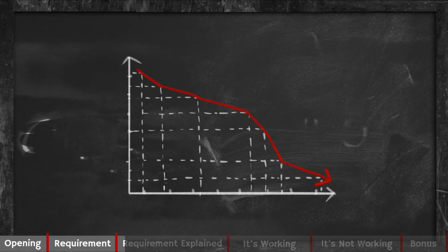The definition of overkill is a sterilization process that demonstrates a 12 spore log reduction in the biological indicator, having a resistance greater than or equal to the bioburden of the product. As we analyze any sterilization process, we're mainly looking at the concentration of the sterilant and the exposure time. The sterilant, in most cases, will be either steam, heat, ethylene oxide, radiation, or some other form of sterilant that's applied to the product. Then you have the exposure time.